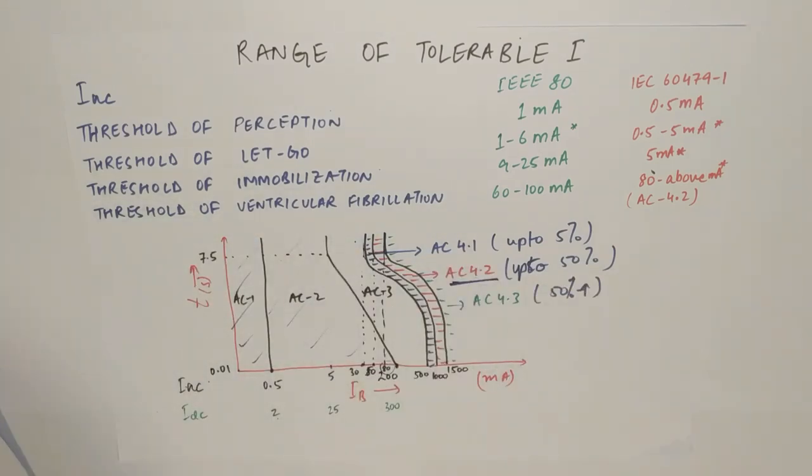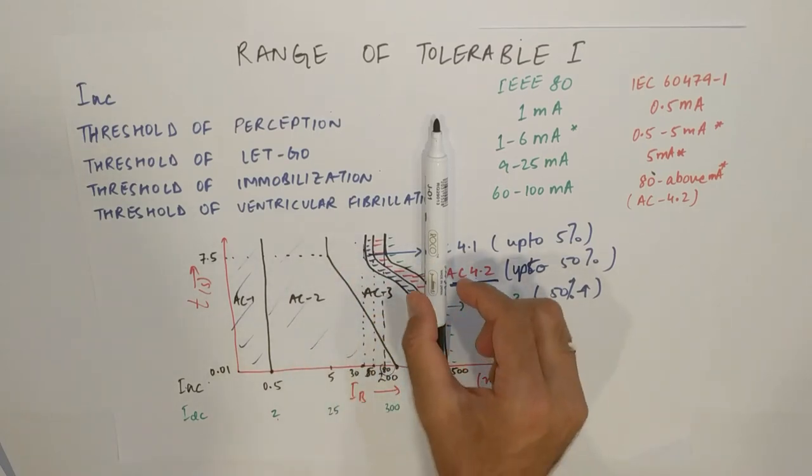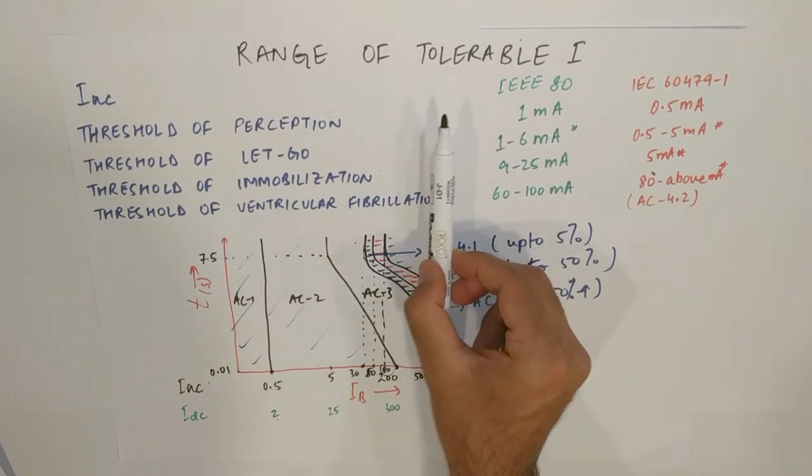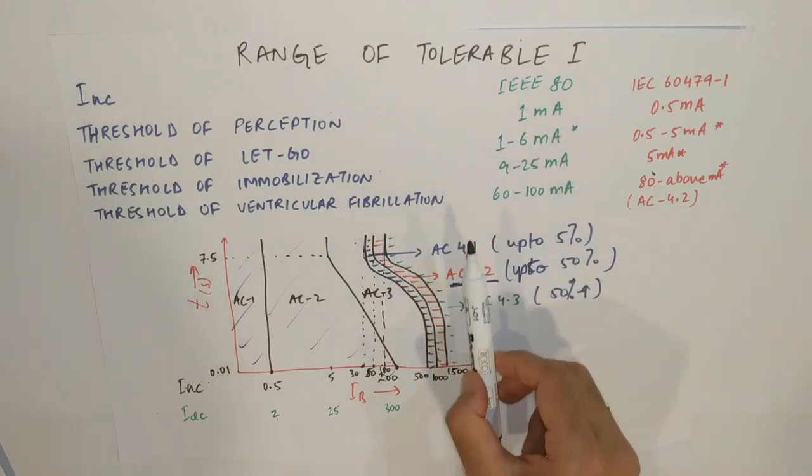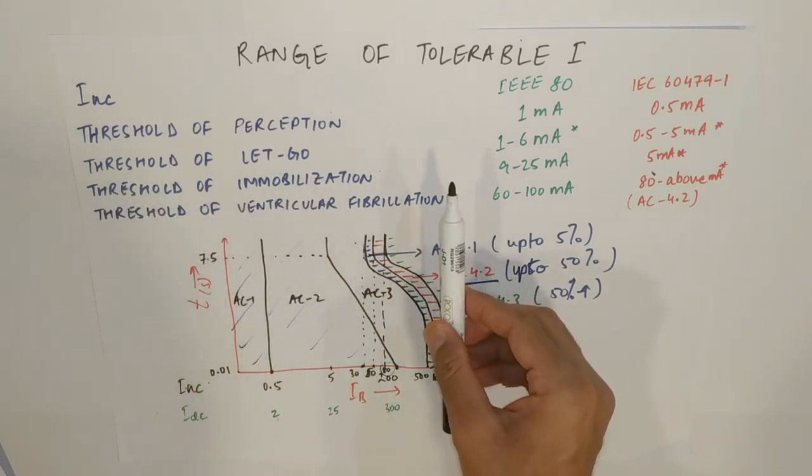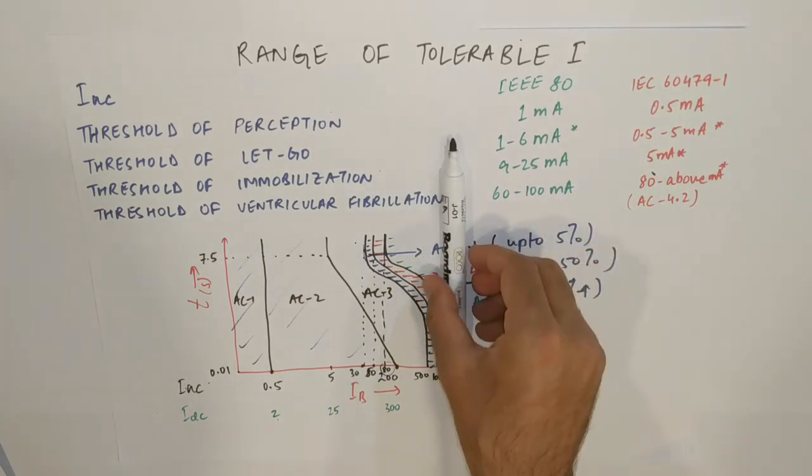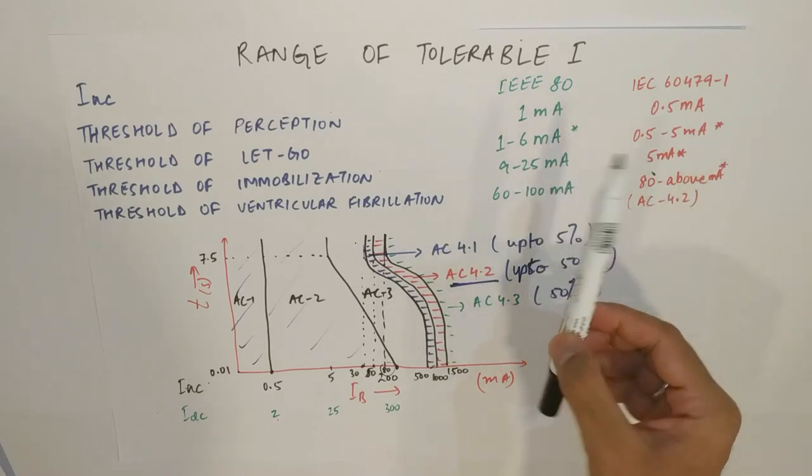There are four types. One is the threshold of perception. Suppose this is the body from which the current is flowing, this marker. And perception means if I touch it and there is current flowing and I feel some tingling effect, some current is flowing through me also. So, this amount is equal to 1 milliamp as per IEEE 80. For threshold of let go, let go means I am holding this, I am touching the equipment, the frame of the washing machine. The current is flowing through me. But still, I can remove my hand. I can remove my hand easily. Not a problem. That is 1 to 6 milliamps, star marked as per IEEE 80. 6 milliamps is for women, 9 milliamps for men.